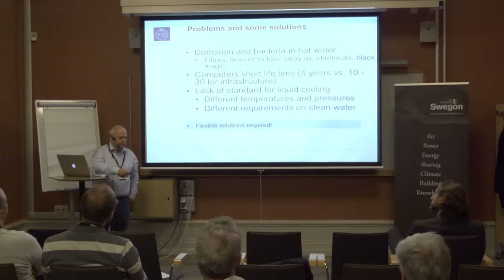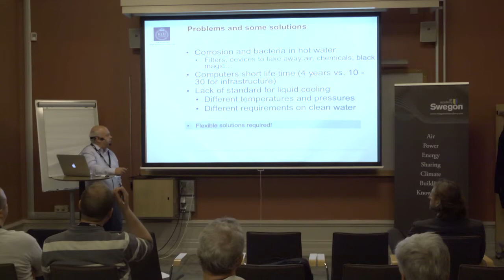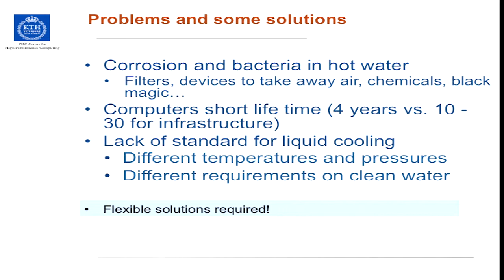But there are also some problems with heat reuse. Computers have a short life cycle, and there's no standardization, so you might need to change some infrastructure when you upgrade the computer or switch to another manufacturer. There's also a problem with corrosion and bacteria in hot water - not an easy problem, we've seen it. Abroad, they normally use chemicals in the water, but we try to avoid that in Sweden for environmental reasons, which can cause corrosion problems. There doesn't seem to be consensus in the industry on how to treat this - it's more black magic than real scientific method, as far as I understand.